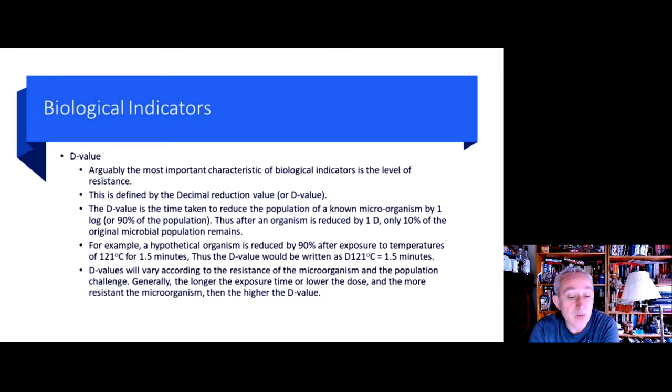Now, D values will vary according to different microorganisms, the temperature, the sterilization process, and the population challenge. So generally, the higher the D value, the longer the time required, or we will need to look at varying the temperature upwards.